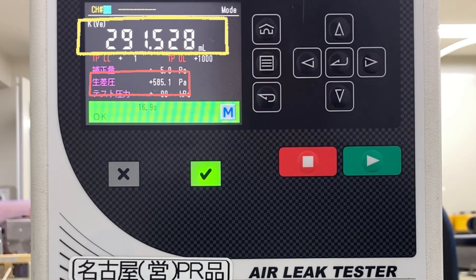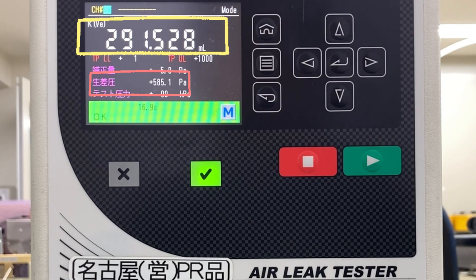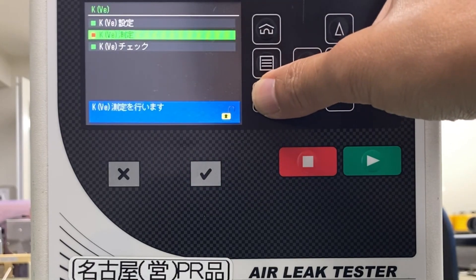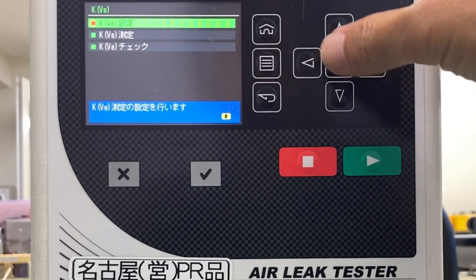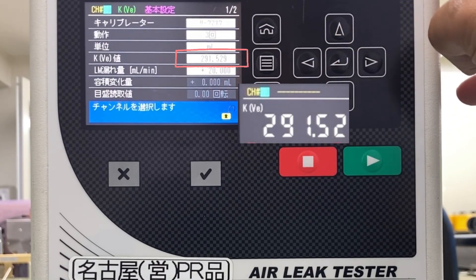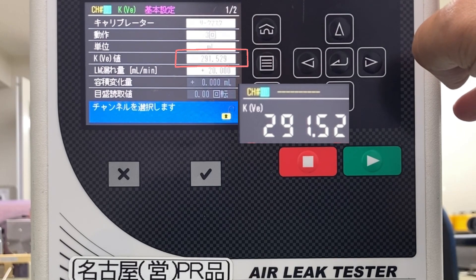The raw differential pressure value was displayed as 585.1 Pascals. From this value, the value obtained in the second measurement is subtracted, and the KVE will be automatically calculated. Select Basic Settings and confirm that the KVE value field contains the value you just calculated.